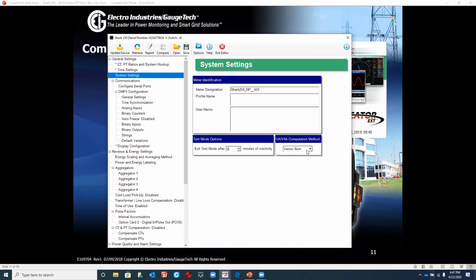The vector sum is just another method of calculation. Vector is a phasor diagram, basically a calculation method for VA and VAh, or arithmetic sum calculation. So you have a choice. You typically leave it at the default, and it doesn't affect the computation other than using any of those methods. You won't see anything in your measurement process.